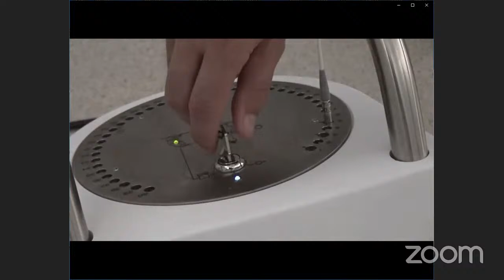The door of the treatment room has to be closed before starting the irradiation. This is the electrometer again. From the afterloader's control computer, a special radiation program has to be loaded for the source calibration. The actual source parameters can be seen on the screen. And then we accept the loaded data.